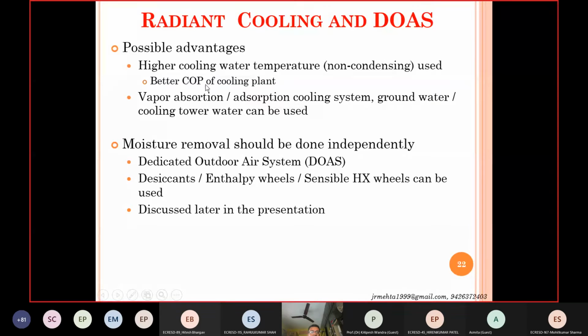With such a higher temperature, systems like vapor absorption and vapor adsorption can be used, because they are not very good at delivering very low temperatures. Otherwise, they will deliver very low COPs. Okay, so now you have opened the option for using other alternative air conditioning systems like vapor absorption and adsorption, and they need less electrical power, and they mainly run on heat, right, which can come from, let's say, solar energy, or it can come from waste heat, and so that option is open.